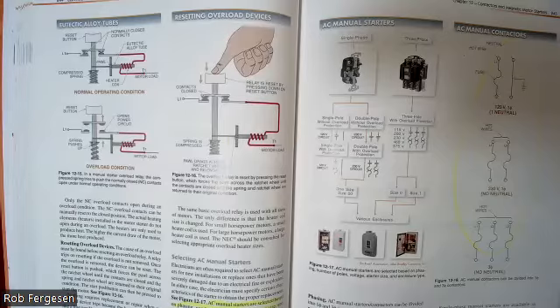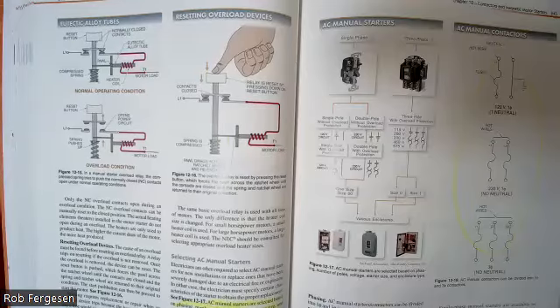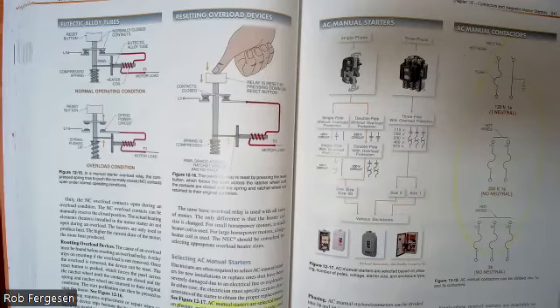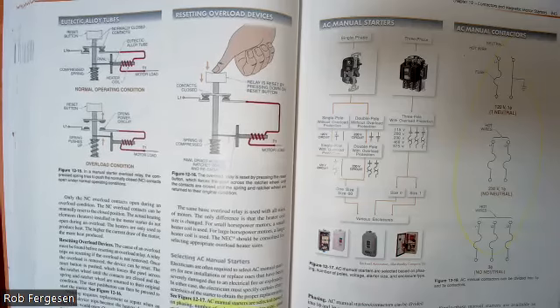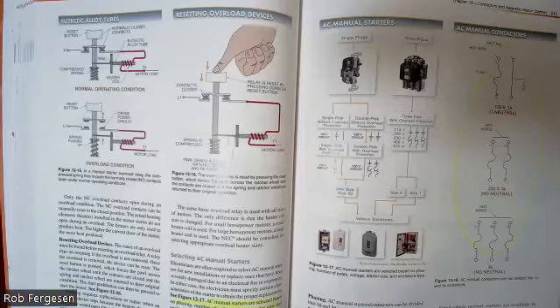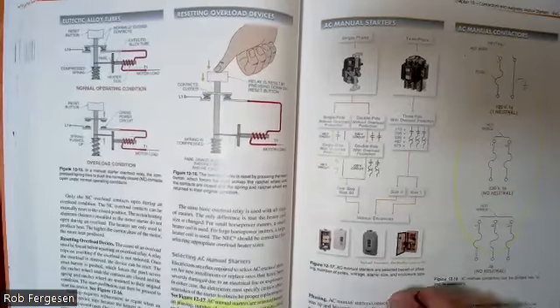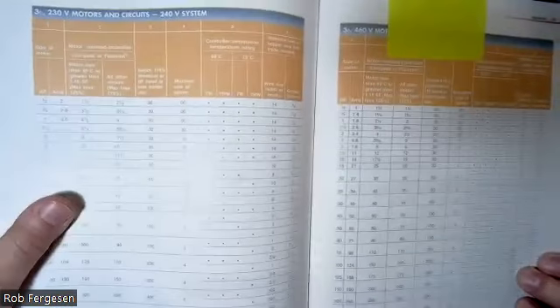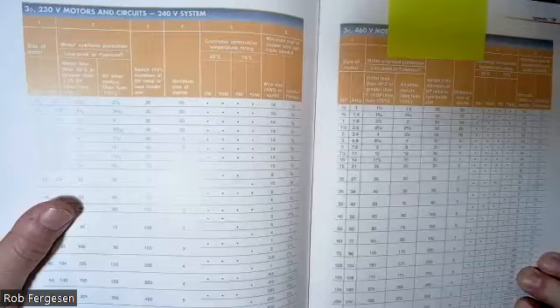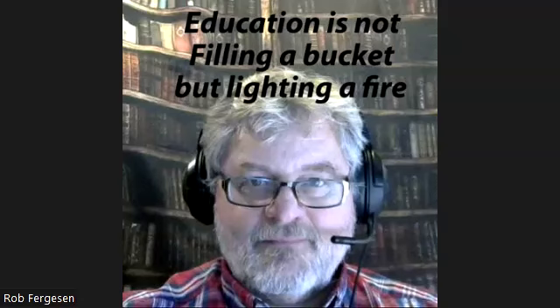Now, I think I said something last week which isn't quite true. I said you usually set your overload based on the motor current, and that's only true for the modern overloads, like the circuit breaker electronic motor overloads. When you're talking about these old school overloads, you always select based on a variety of factors. In the appendix, they give you a table for that. And that table is on pages 728 and 729. So you would pick your motor size based on its horsepower. They'll tell you what probably the typical current is for that motor. And then it will make a suggestion for your overload protection based on factors of either high heat or regular heat situation.